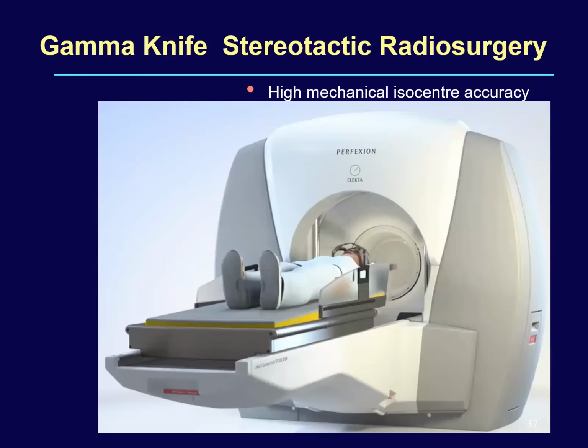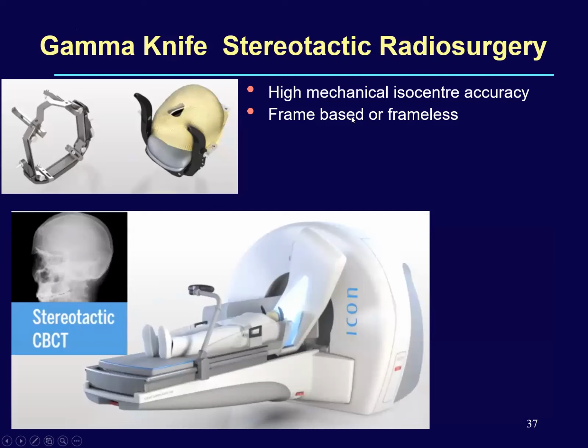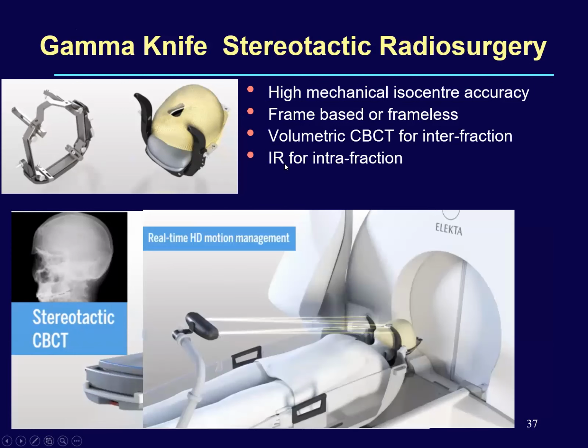Finally, a stereotactic radiosurgery unit like the Gamma Knife Perfexion, which relies highly on mechanical isocenter accuracy, is also now thought to need fractionation of these treatments into fewer fractions, 3 or 5, and has been reintroduced with the mask system and cone beam CT for interfraction and infrared for intrafraction motion management strategies.